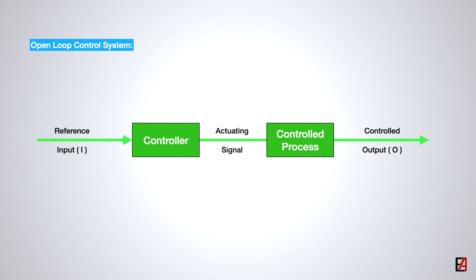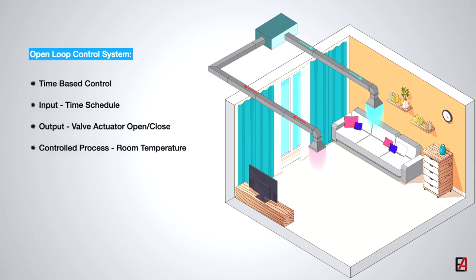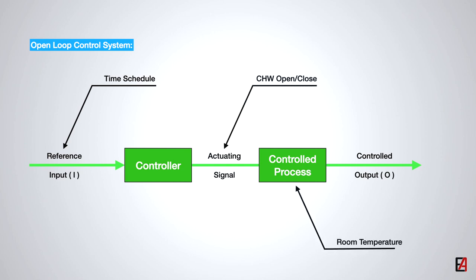To understand this, let's take a living room conditioned by a fan coil unit. Consider this FCU works on a time-based temperature control sequence, where the chilled water control valve is opened and closed based on a defined time interval to maintain the room temperature. The defined time schedule is the input to the controller, the actuating signal is the output to open or close the control valve actuator, the control process is the room temperature control, and the controlled output is the amount of chilled water fed to the cooling coil.